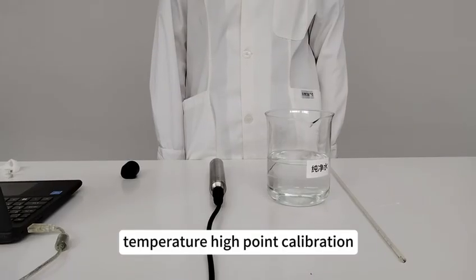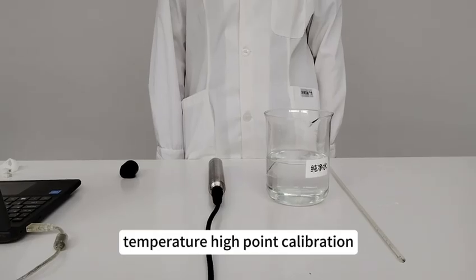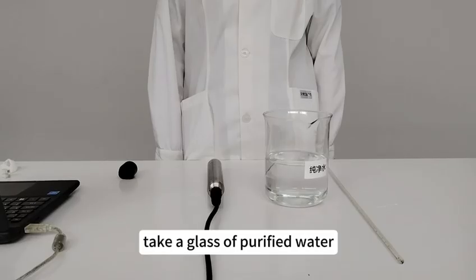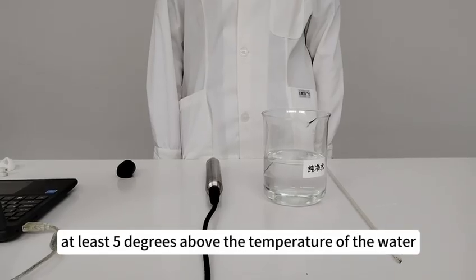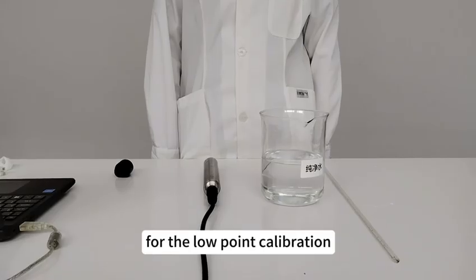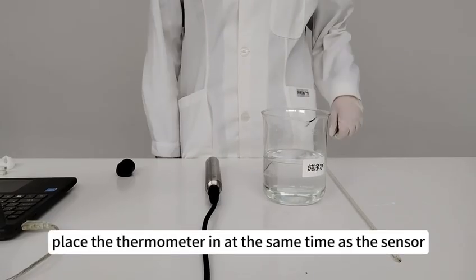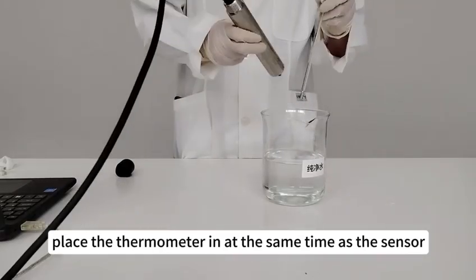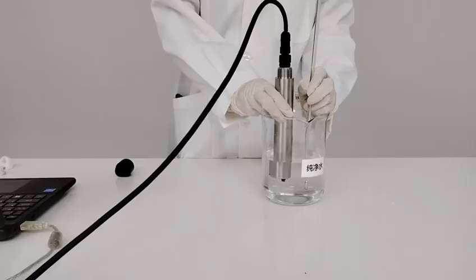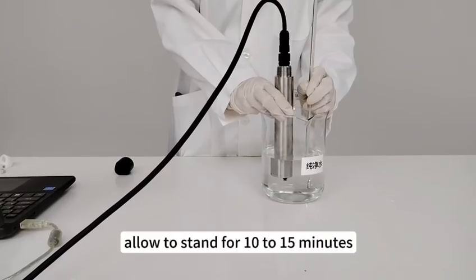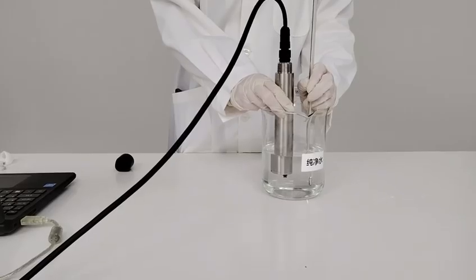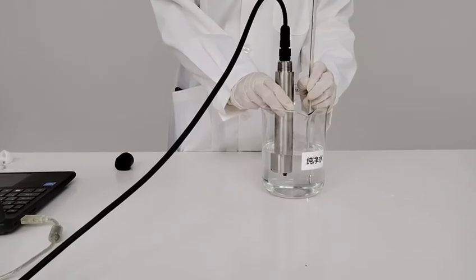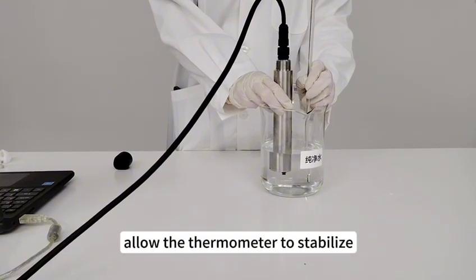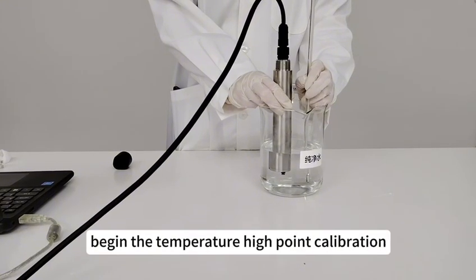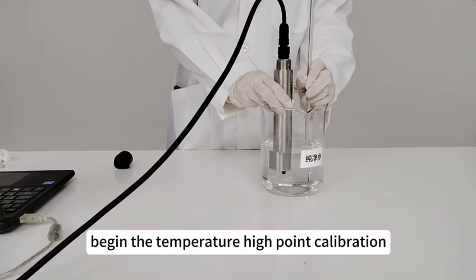Temperature high point calibration. Take a glass of purified water at least 5 degrees above the temperature of the water for the low point calibration. Place the thermometer in at the same time as the sensor. Allow to stand for 10 to 15 minutes. Allow the thermometer to stabilize. Begin the temperature high point calibration.